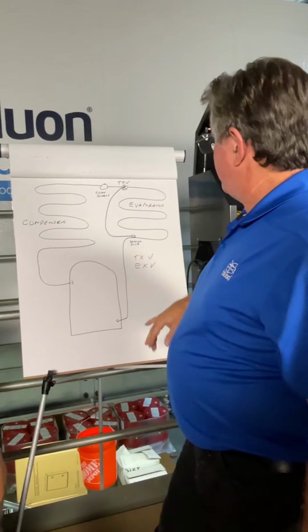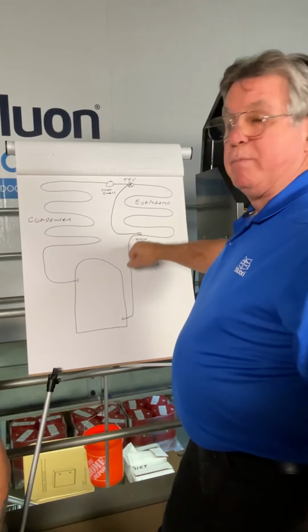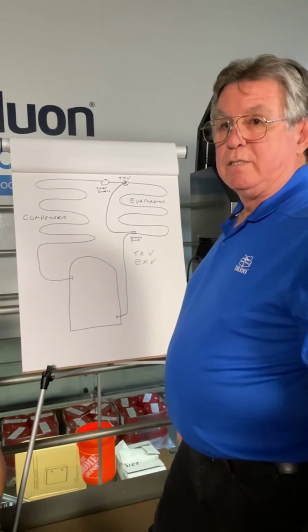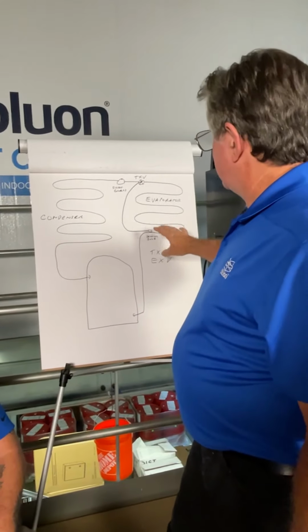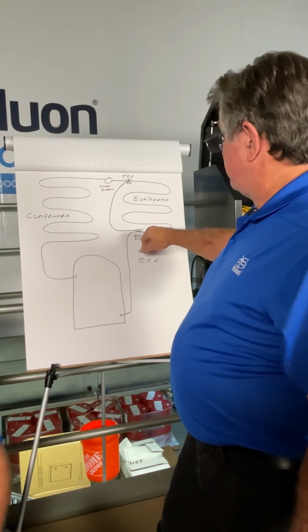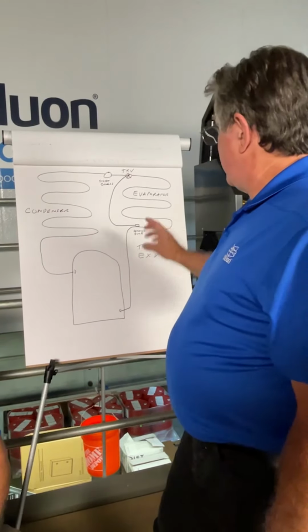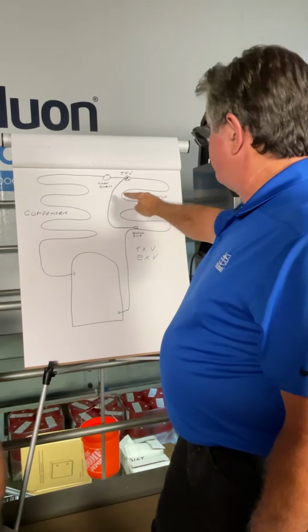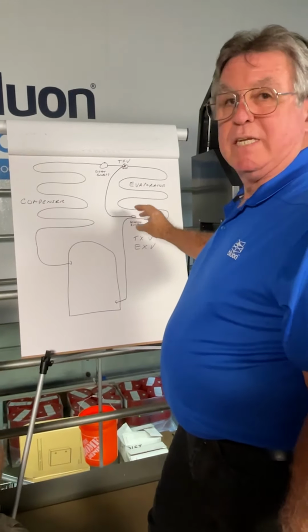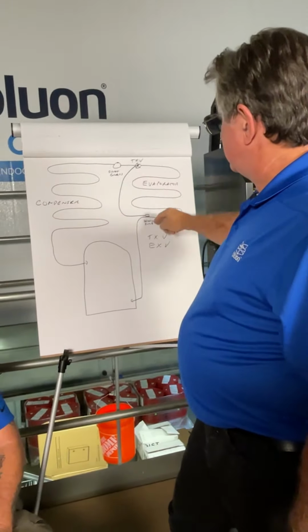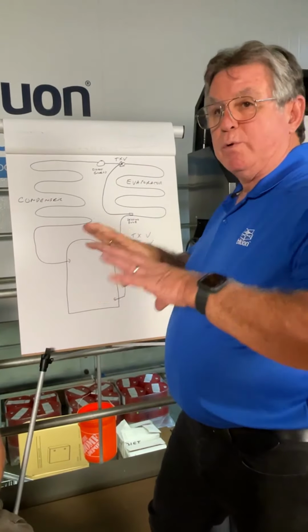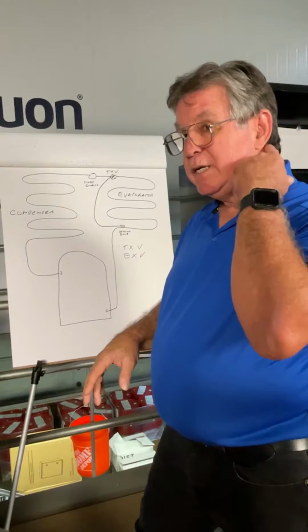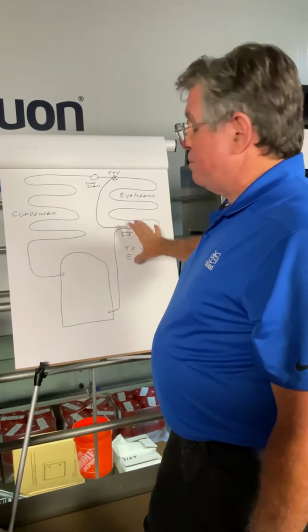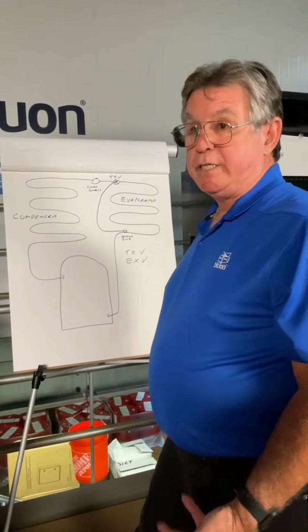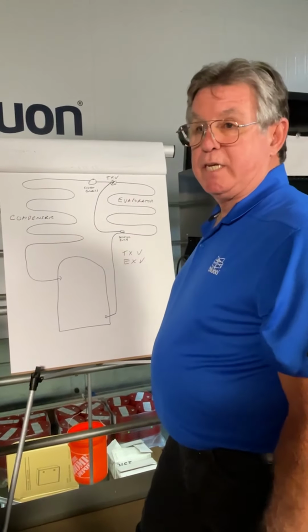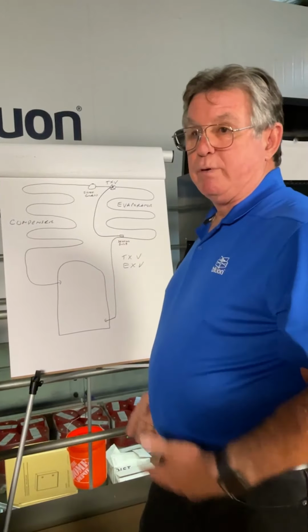Now, this thermostatic expansion valve has got a sensing element down here reading the suction coming off the evaporator. And typically you set these up for about 12 degrees. So what happens is, if I'm not opening this valve far enough, this valve is going to see that. It's going to exert a pressure on the TXV, and it's going to open the valve. So it's always adjusting based upon conditions. All right. So if my air temperature changes, if my air volume changes, I'm going to get changes taking place here in the evaporator, and the valve is going to respond to that.